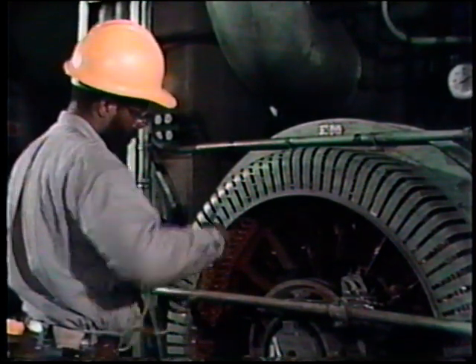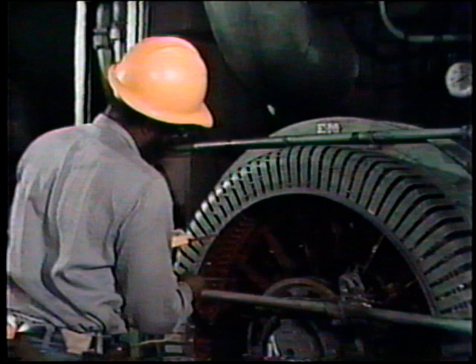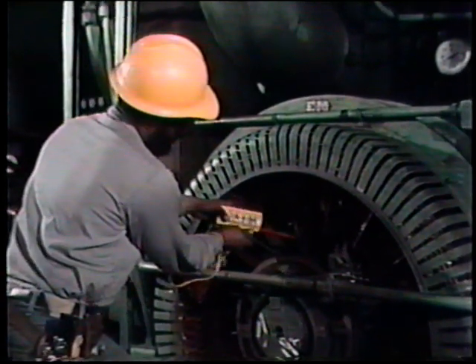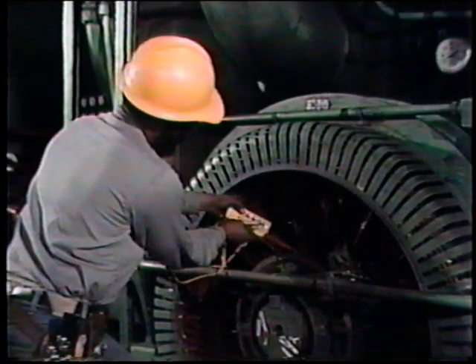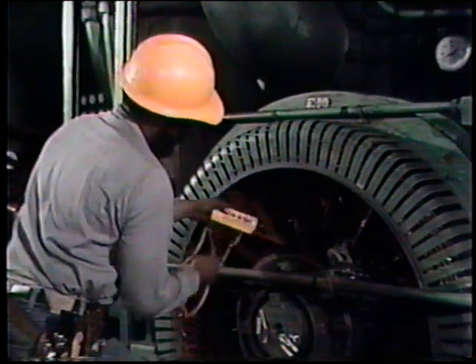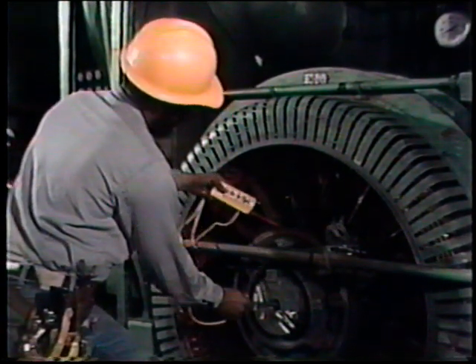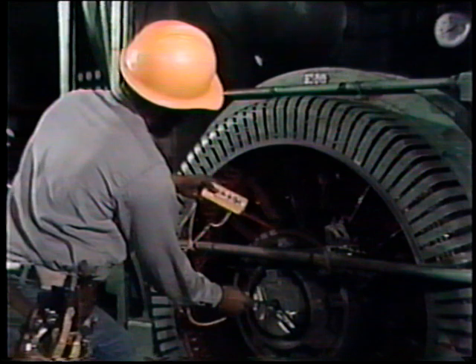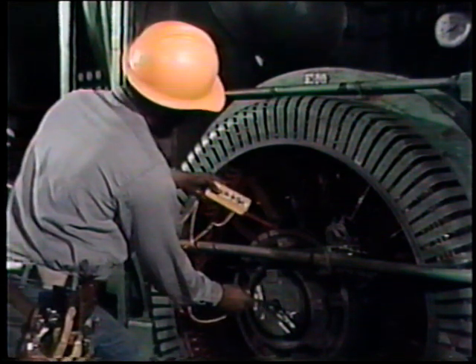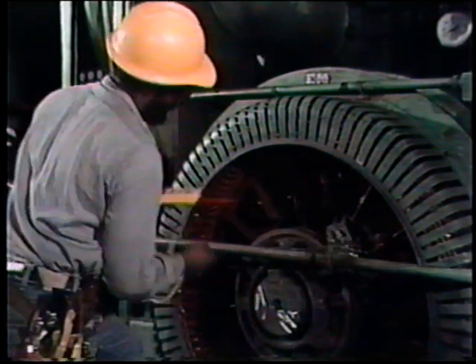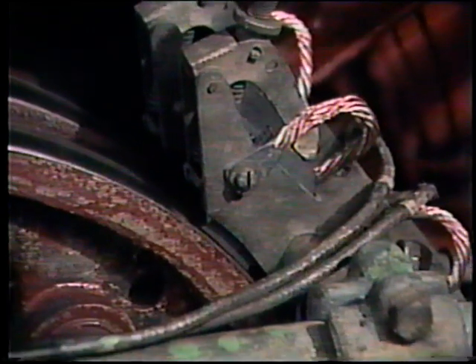Next, use a voltage tester that has been checked for proper operation to verify that the motor is de-energized and hasn't any charge on it. Test line to line and line to ground at the slip rings of the motor. A 0 voltage reading for both indicates that the rotor is safe to work on. Then begin your inspection by examining the brushes and brush rigging.